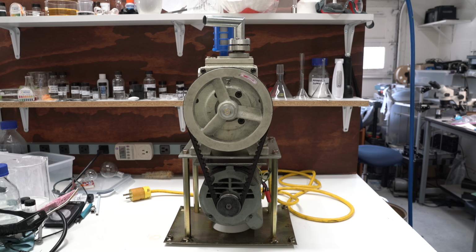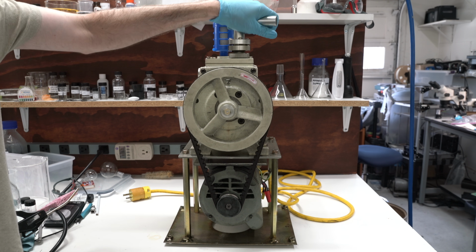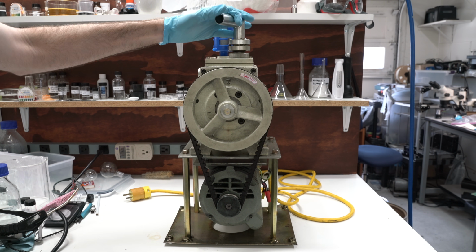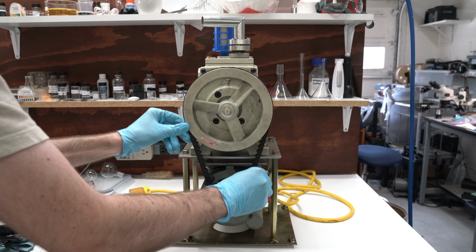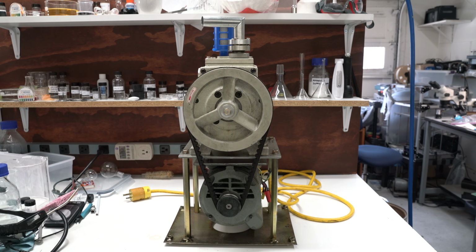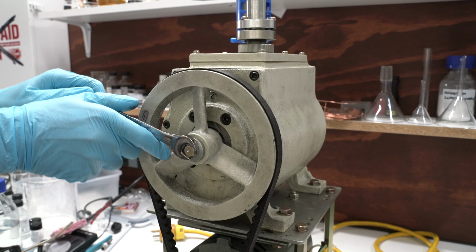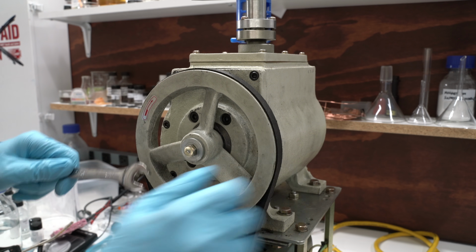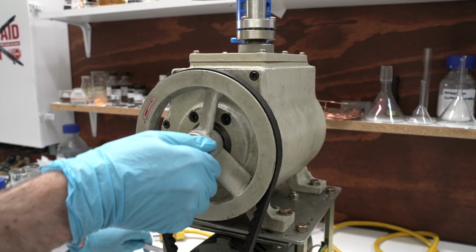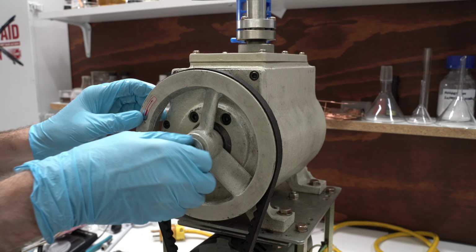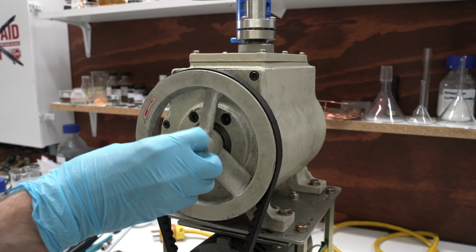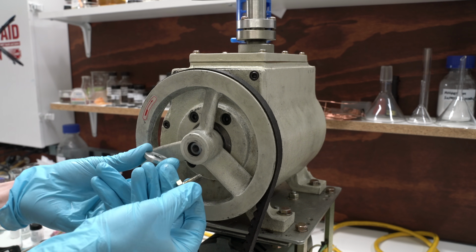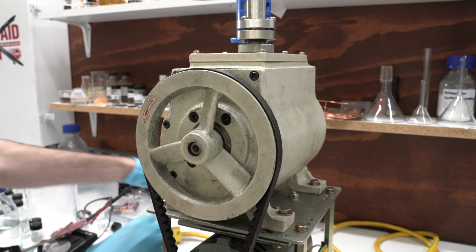If you recall, I tested the pump earlier and verified that it went down to 10 millitorr. However, I didn't check that it stayed that low. You see, when a pump is cold, the oil viscosity is high, and so the thick oil inside can effectively seal tiny gaps. As the pump runs, the oil warms up and becomes more free-flowing, and suddenly, any tiny gaps